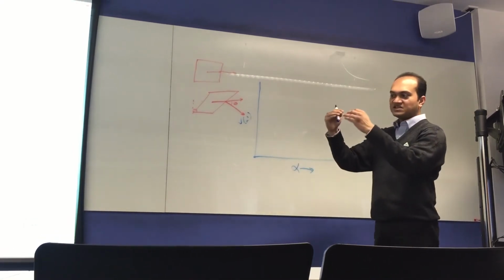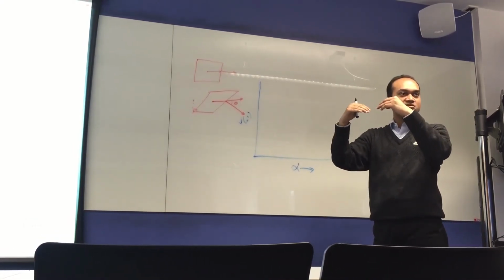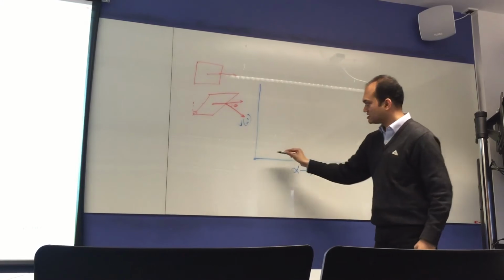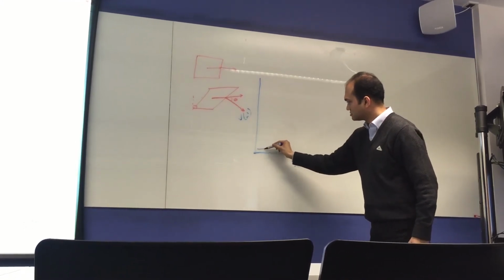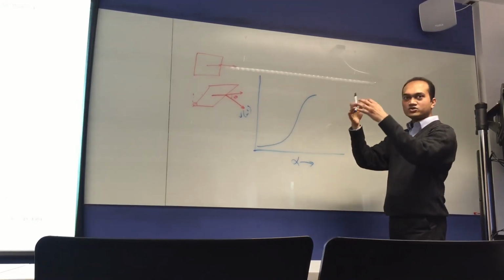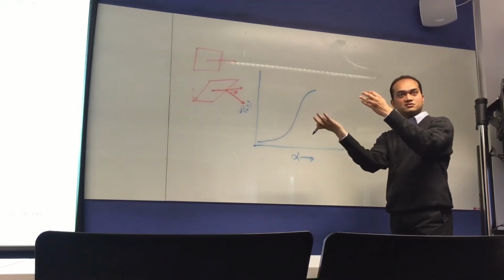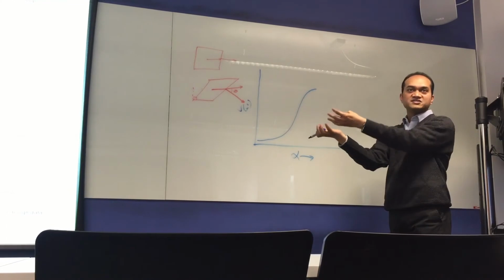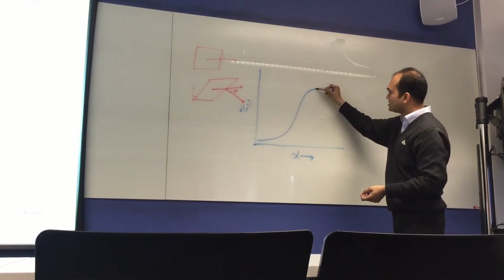Okay. When the rotors start disengaging, they start sucking gas, and the suction starts. It reaches to a maximum point, and then on the opposite side, diagonally opposite side, the rotors start engaging again, and the volume starts reducing.